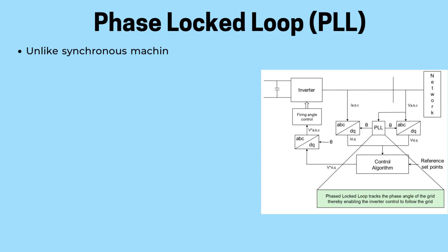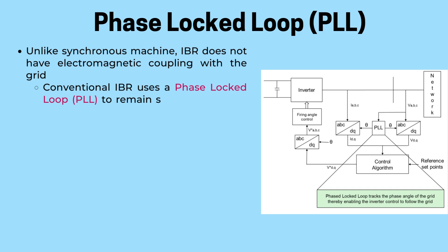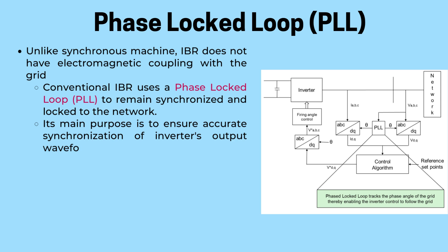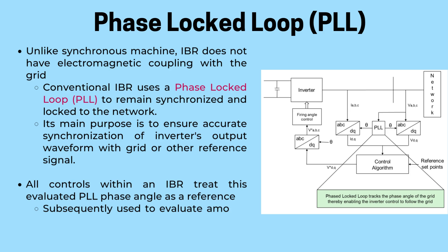In the world of power systems, synchronization is a crucial aspect of ensuring that different devices and resources operate in harmony. In the case of inverter-based resources, which lack the electromagnetic coupling with the grid found in synchronous machines, a phase-locked loop comes into play. The PLL serves as the backbone for keeping IBRs synchronized and locked to the network, allowing for accurate alignment of the inverter's output waveform with the grid or another reference signal. Within an IBR, the evaluated phase angle of the PLL serves as a reference for all its controls, determining the amount of current the IBR needs to inject into the system.